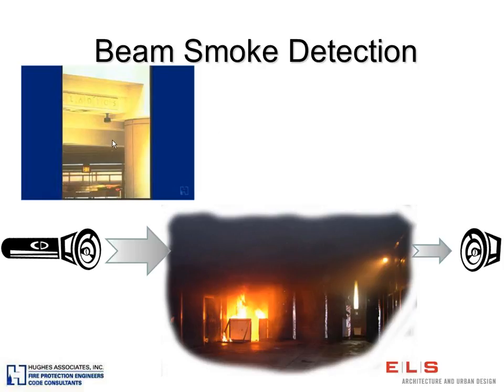So in this photo right here, what you see is half of the beam detector, essentially. There are two pieces that look just like this one. One is a transmitter and one is a receiver. I can't tell you from looking at this one which side it is. I can only tell you that there's one. They look the same. One transmits and one receives. And the way they work is like this. Here is your transmitter. It transmits the light across to its receiver, and the receiver observes it. When the beam becomes blocked by particles of combustion, it will then sound an alarm.